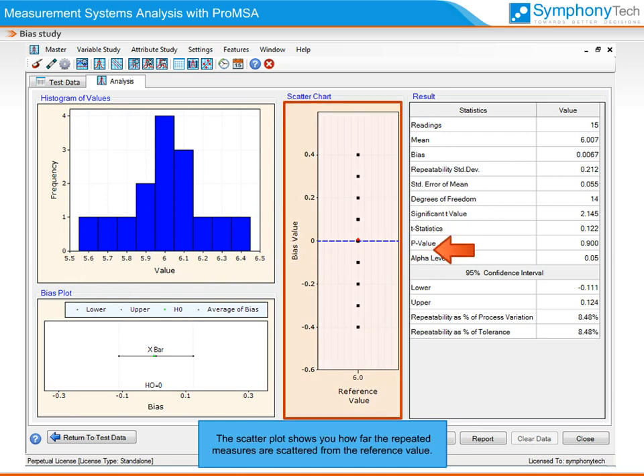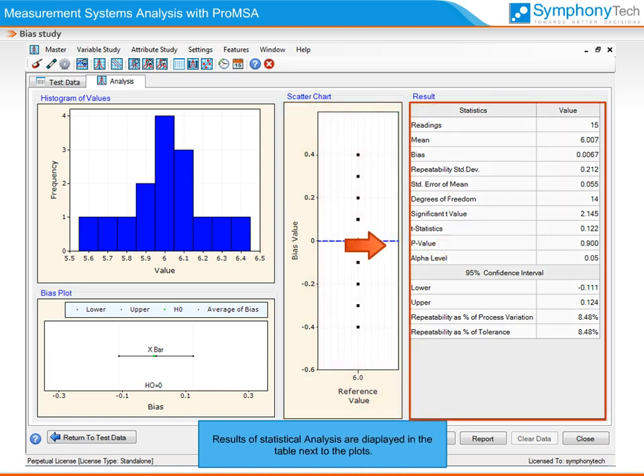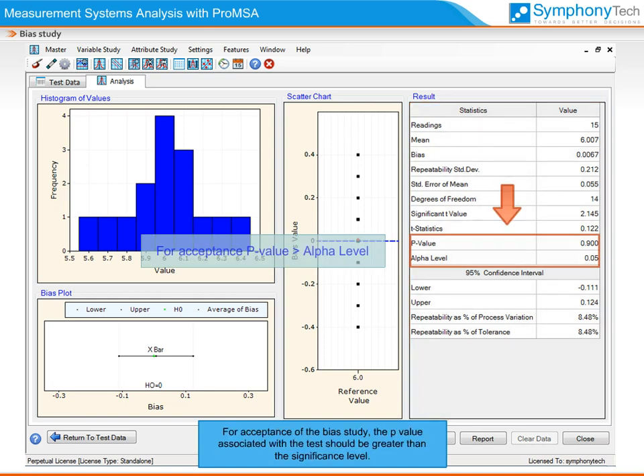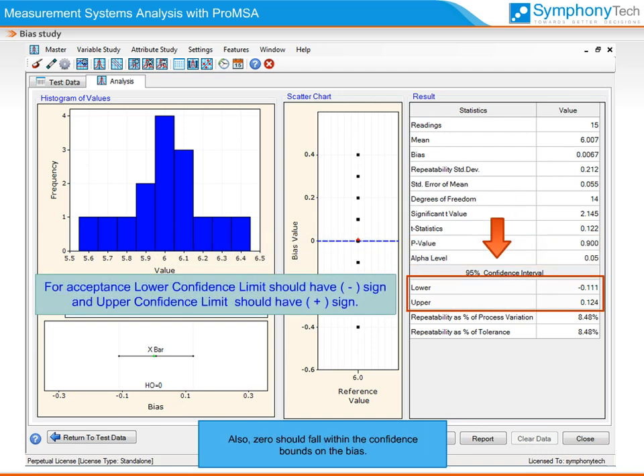The scatter plot shows you how far the repeated measures are scattered from the reference value. A close scatter shows good repeatability. Results of statistical analysis are displayed in the table next to the plots. For acceptance of the bias study, the p-value associated with the test should be greater than the significance level. Also, zero should fall within the confidence bounds on the bias.